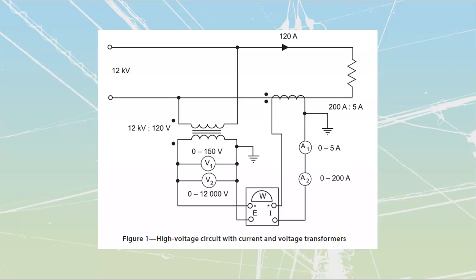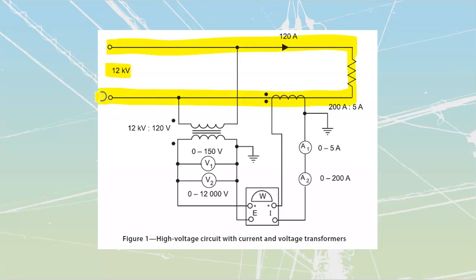Let's start by examining our main line. We've got a 12 kV line over here, and so we are going to go and take some readings from that. Now, 12,000 volts is ridiculously high to go and have to run any sort of a metering system on. So we don't want to have a voltmeter or ammeter rated for that. We're going to go and use these CTs. If I take a look, this yellow path over here is going to be my primary current path. Everything else is just simply seen as a load.